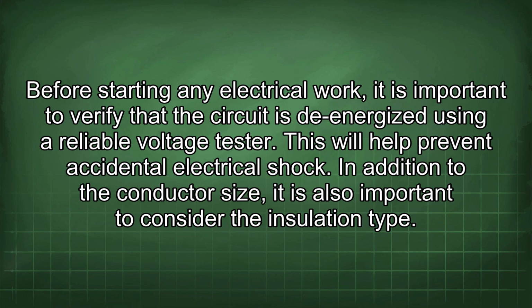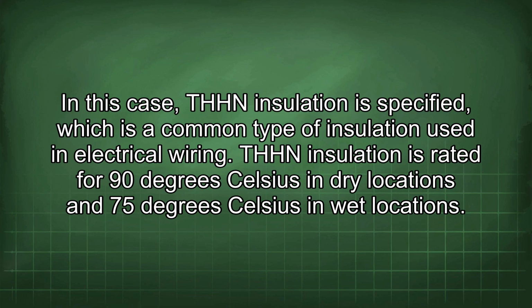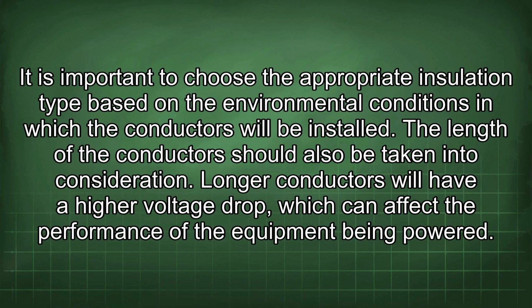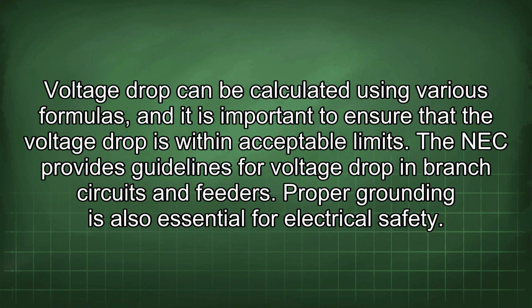In addition to the conductor size, it is also important to consider the insulation type. In this case, THHN insulation is specified, which is a common type of insulation used in electrical wiring. THHN insulation is rated for 90 degrees Celsius in dry locations and 75 degrees Celsius in wet locations. It is important to choose the appropriate insulation type based on the environmental conditions in which the conductors will be installed. The length of the conductors should also be taken into consideration. Longer conductors will have a higher voltage drop, which can affect the performance of the equipment being powered. Voltage drop can be calculated using various formulas, and it is important to ensure that the voltage drop is within acceptable limits. The NEC provides guidelines for voltage drop in branch circuits and feeders.